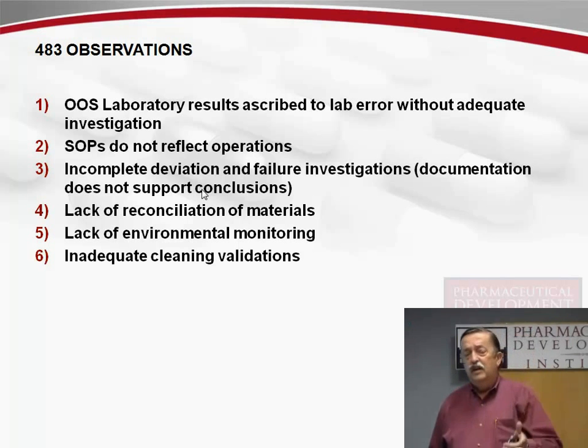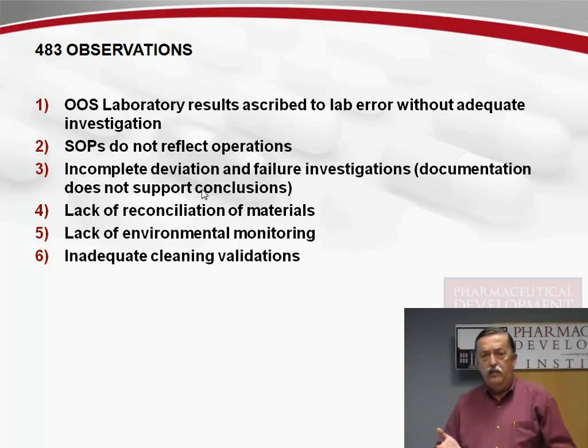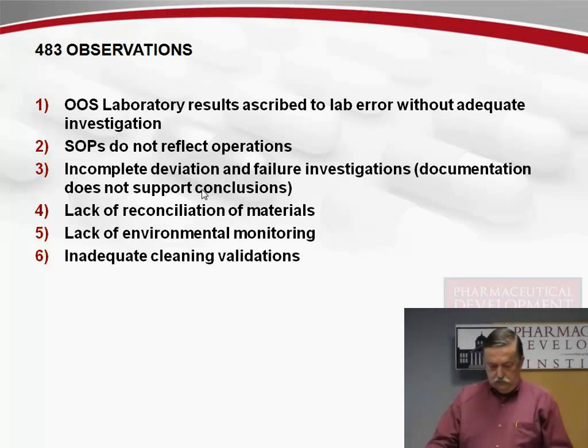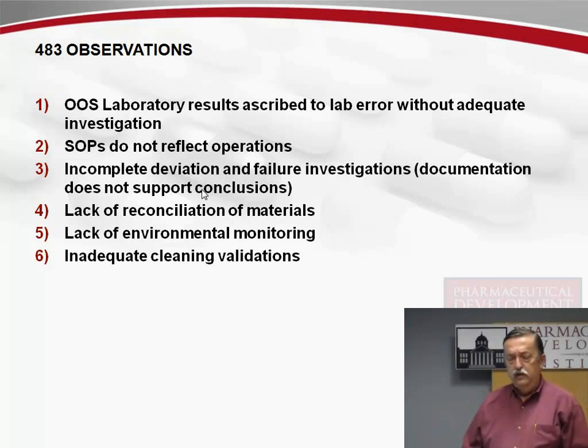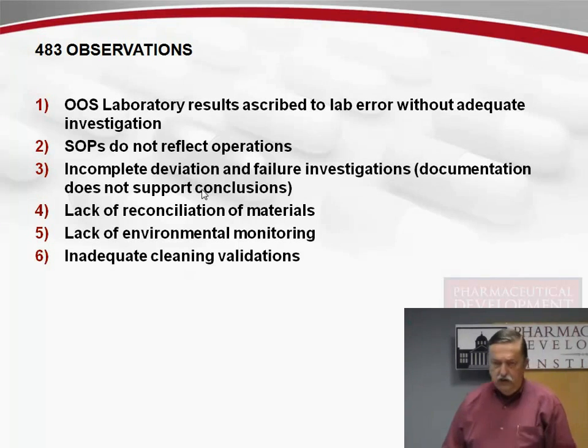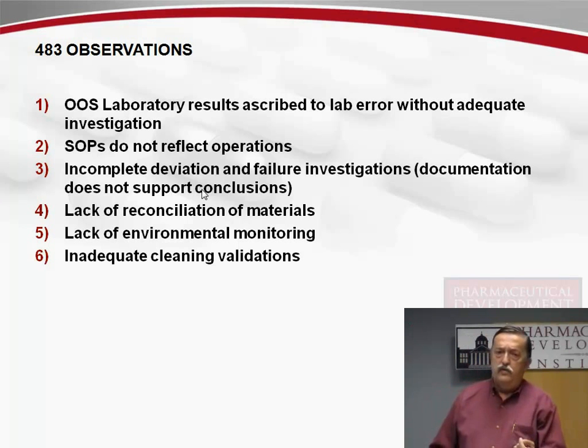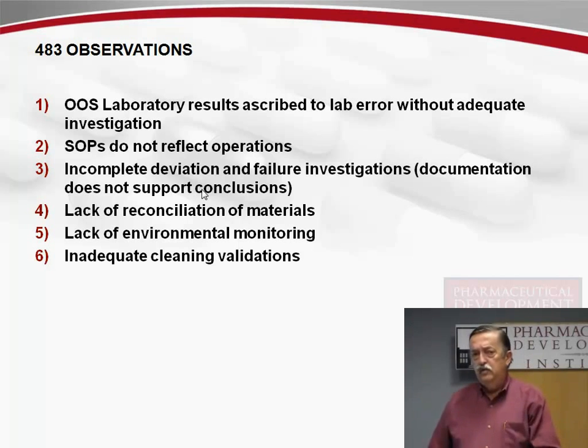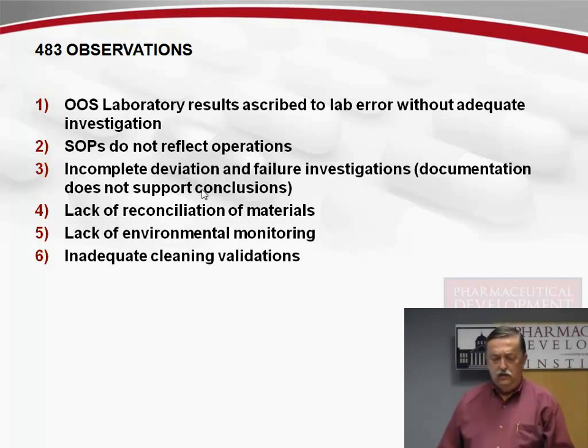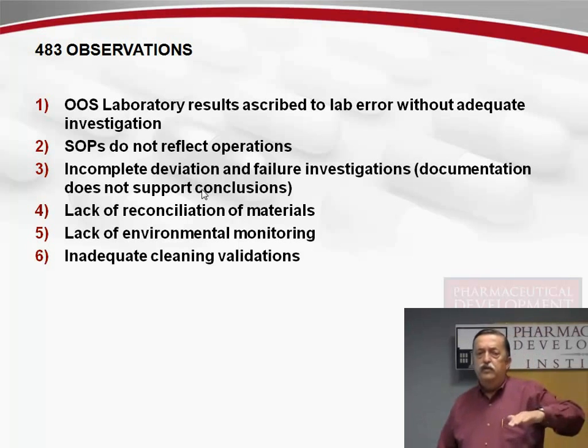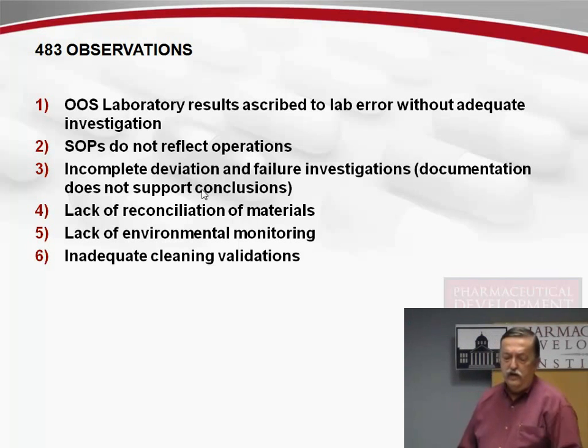But where they fall down is that the analytical procedures used to evaluate residuals, such as cleaning products, need to be validated — but so does the collecting process. They probably take a cloth swab and wipe down a section of equipment to sample for residuals. You have to validate that sampling procedure, and you need to validate the extraction procedure used to extract any residuals from that cleaning swab. There are a number of additional levels of evaluation that need to be performed as part of a cleaning validation.